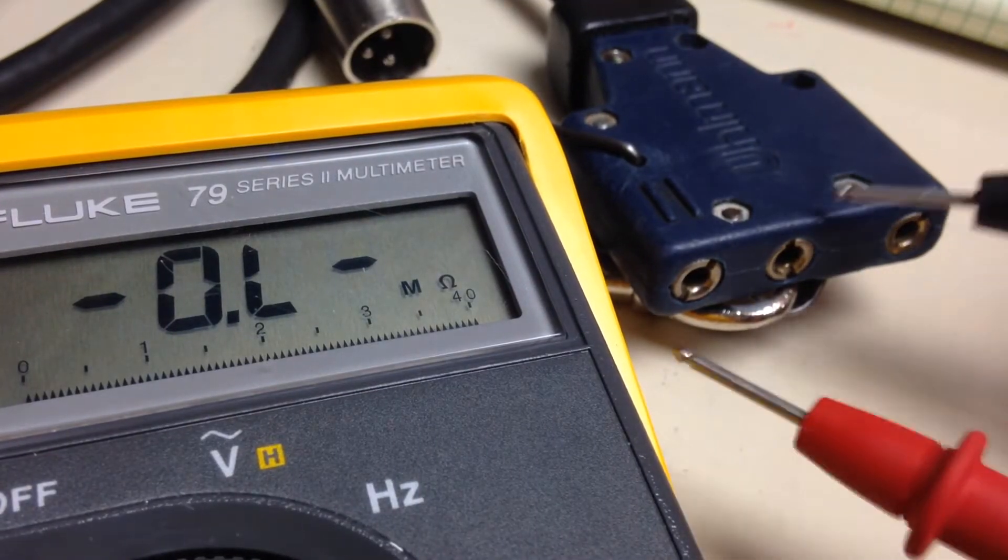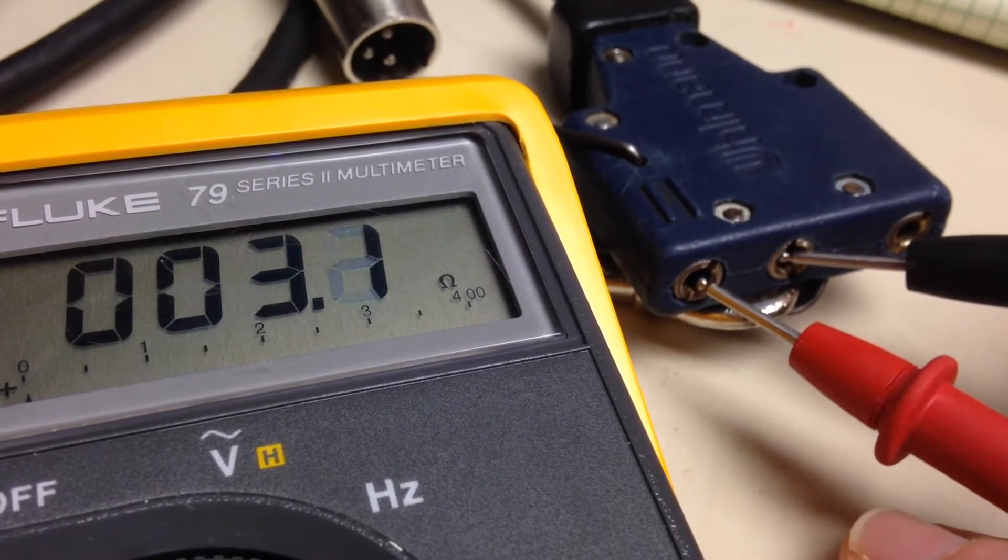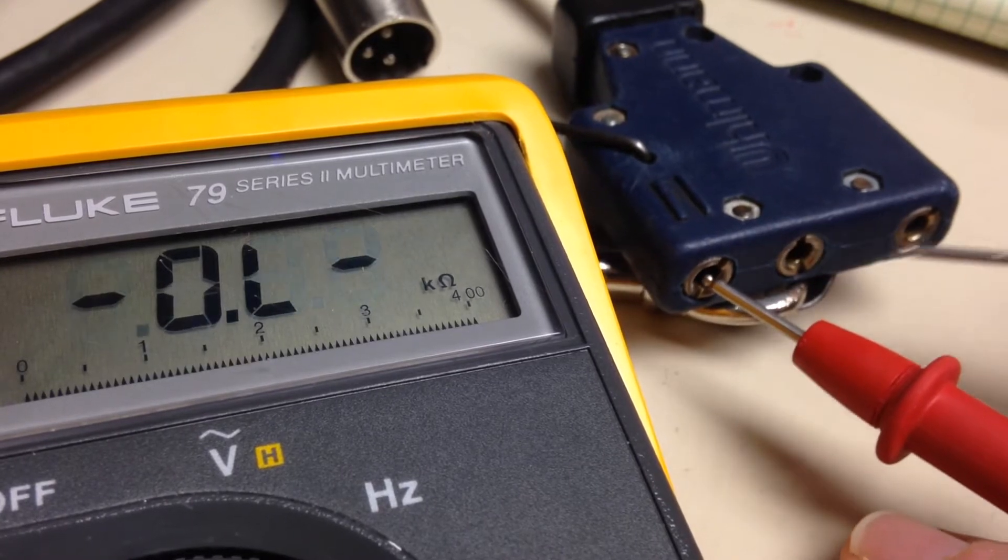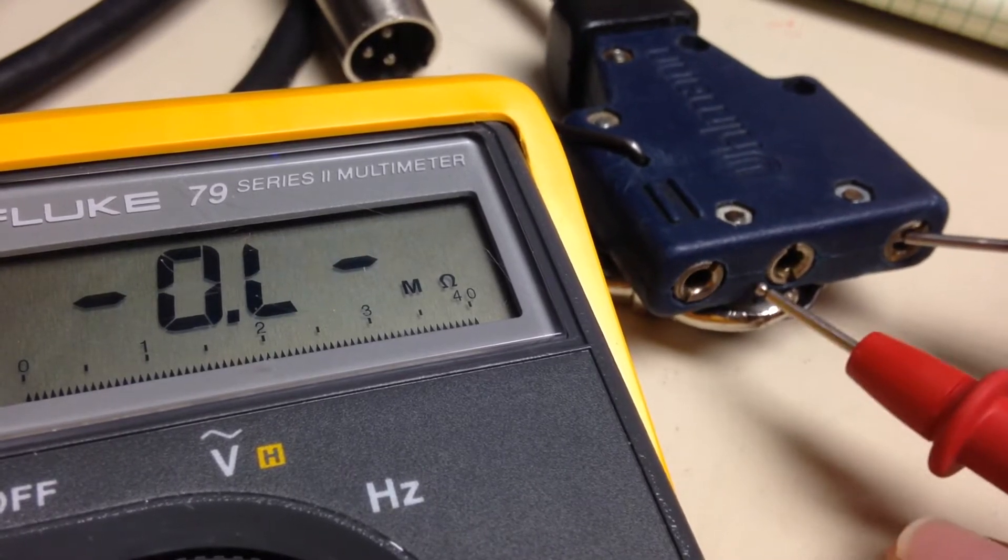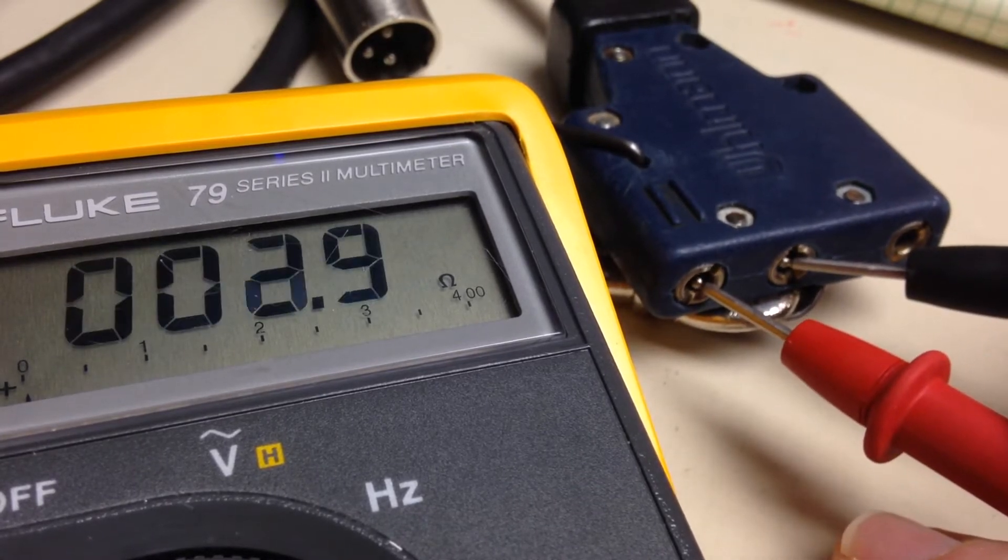I can take my multimeter here and let's probe between the A and the B lines. This is where the short is. It should be an open, but nope, we're getting around two, three ohms of resistance. My probe from A to C, it's an open, and B to C, it's an open. But we go back here, and there's definitely a short.